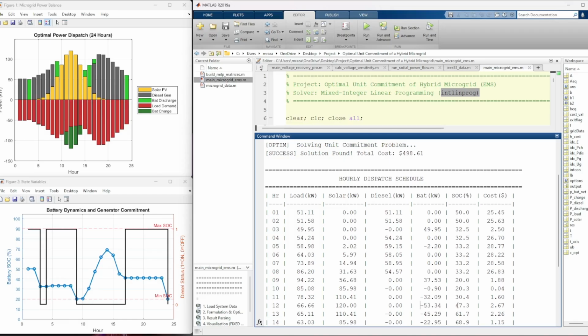And our battery SOC is 47.3, and all our power is taken from the solar. So we are serving 66 kilowatts in the form of load, and the other kilowatts go to charge our batteries, because our solar is not fully efficient and we may add a few noise over there. So that's why this number is a little low, and the cost we are getting here is 2.67.